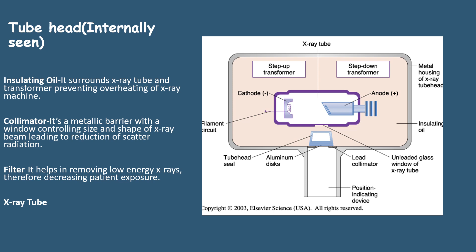The parts present internally in the tube head consist of insulating oil, collimator, filter, and x-ray tube. The insulating oil surrounds the x-ray tube and transformer and prevents overheating of the x-ray machine. The space is filled with the insulating oil.